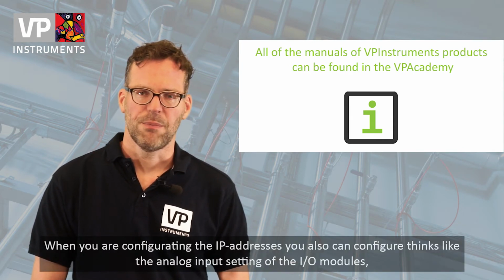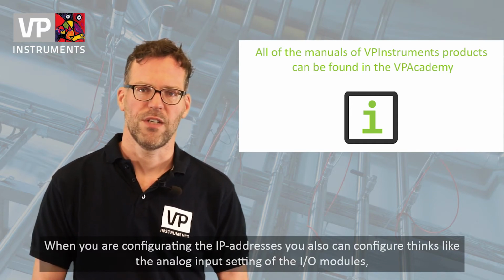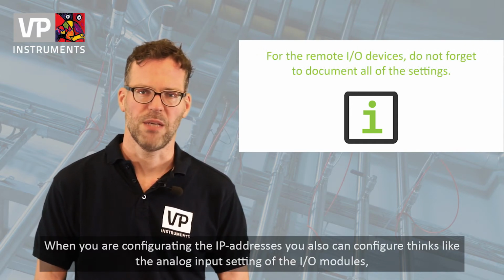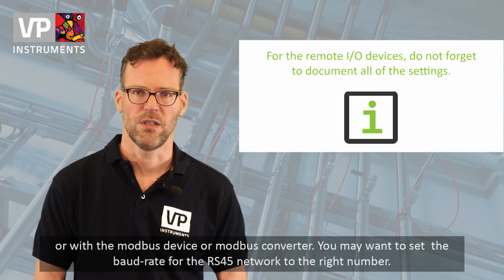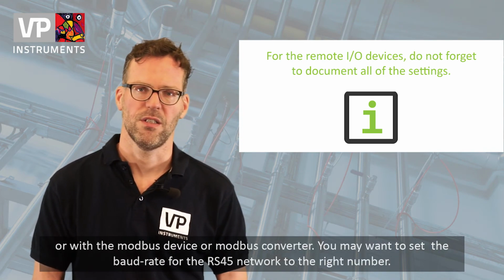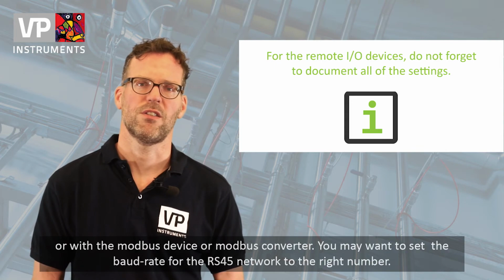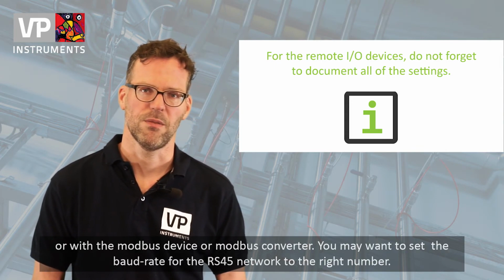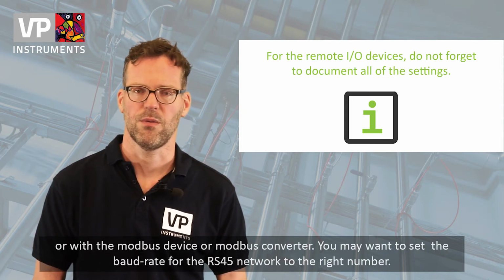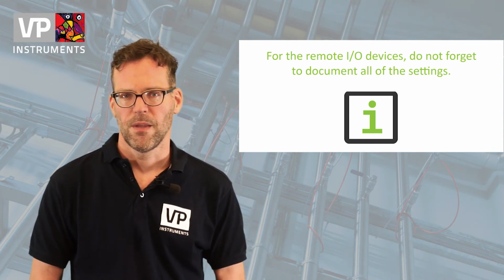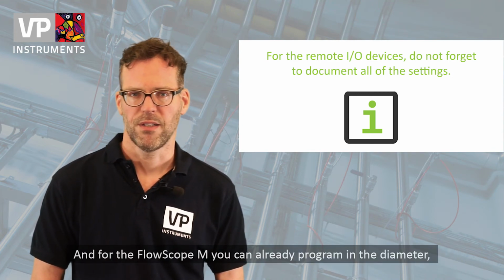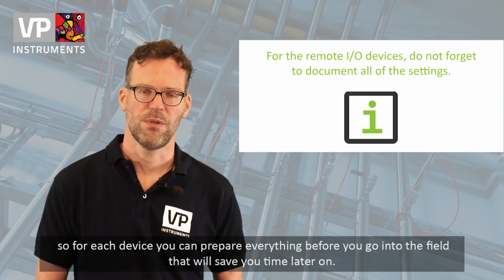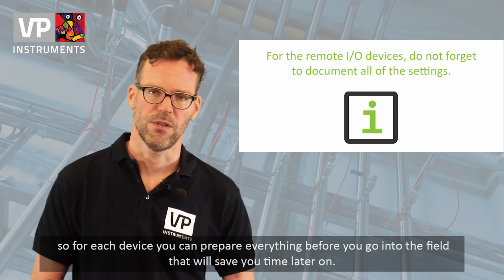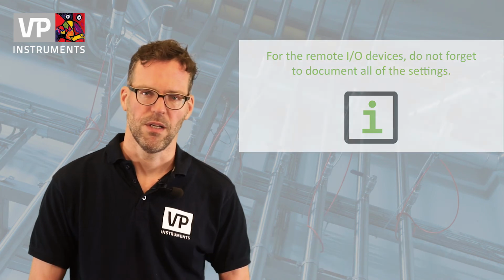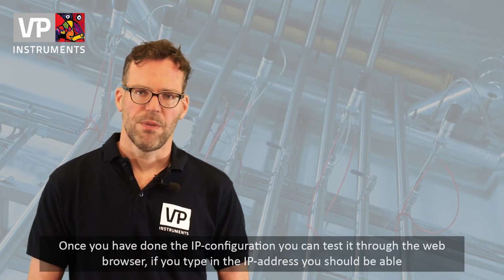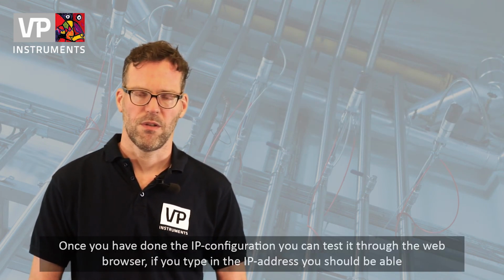When you're configuring the IP addresses, you also can configure things like the analog input settings of the I/O modules, or with a Modbus converter, you might want to set the baud rate for the RS-485 network at the right number. And for a Flowscope M you can already program in the diameter. So for each device you can prepare everything before you go into the field, and that will save you time later on. Once you've done the IP configuration, you can test it through the web browser.